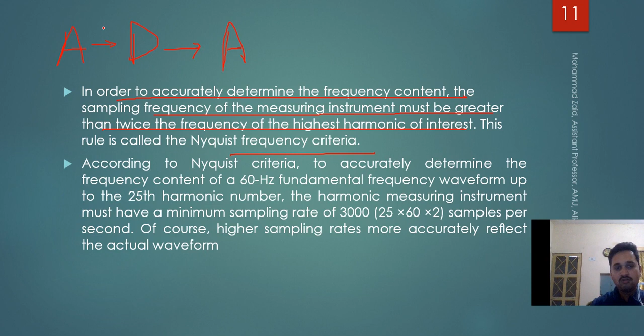So that's why I told you that for a harmonic analyzer you need to be very, very careful. In order to accurately determine the frequency component, the sampling frequency of the measuring instrument must be greater than twice the frequency of harmonic of interest. This is called the Nyquist criteria. Because your equipment, this harmonic analyzer, will convert analog to digital and then again digital to analog. So this is a process in which an ADC, analog to digital converter, and DAC, digital to analog converter, will be involved.